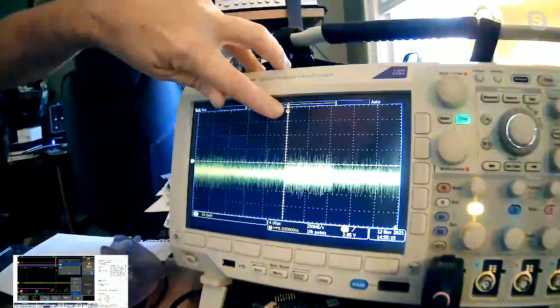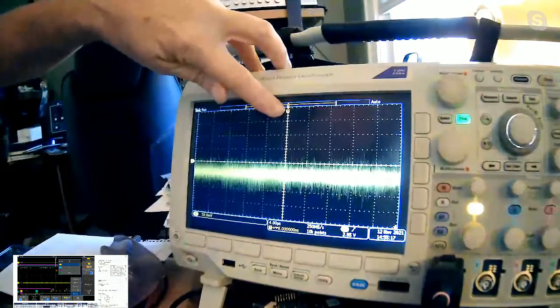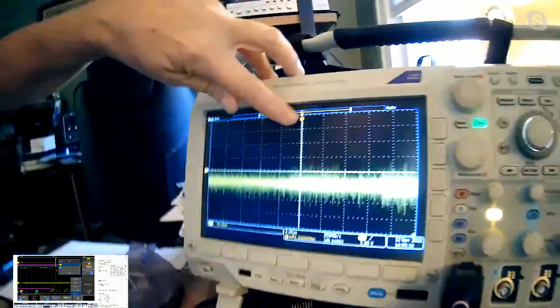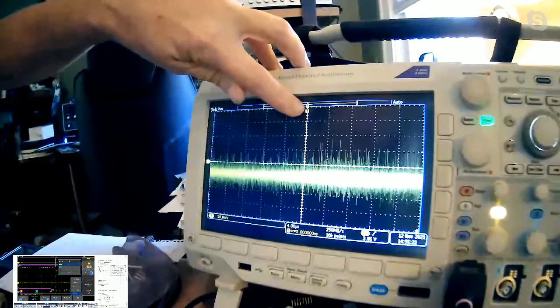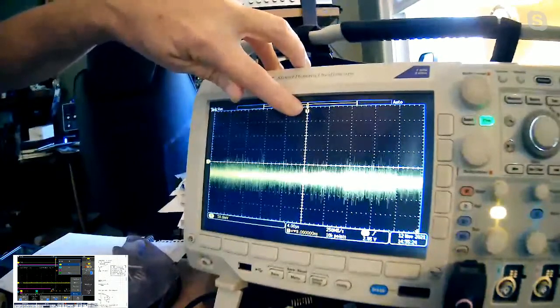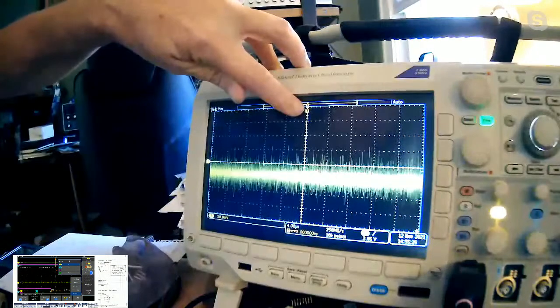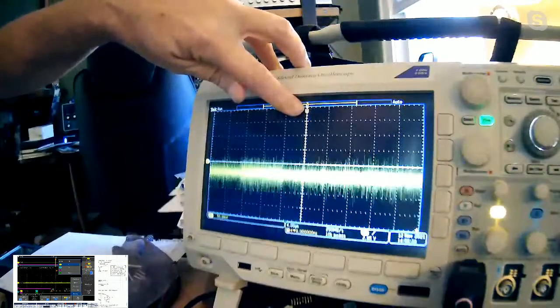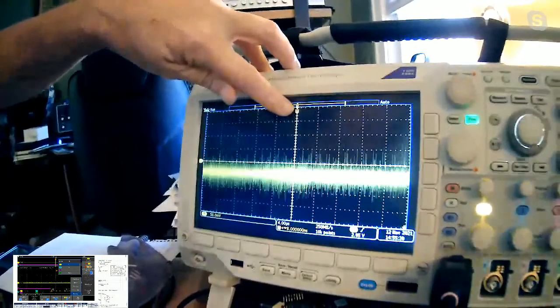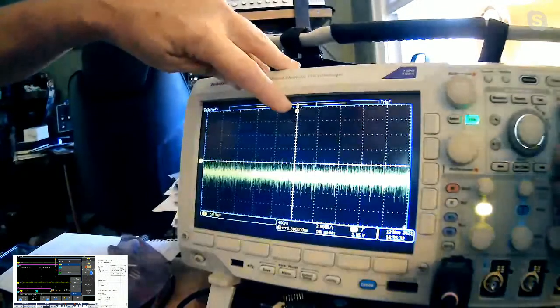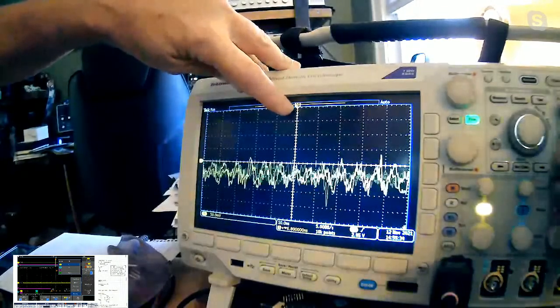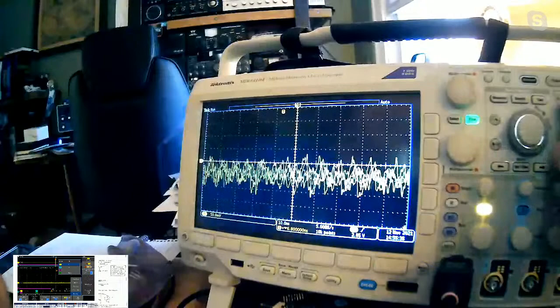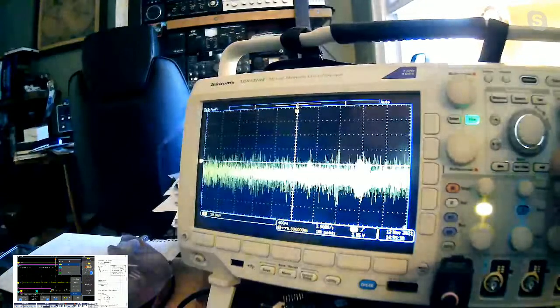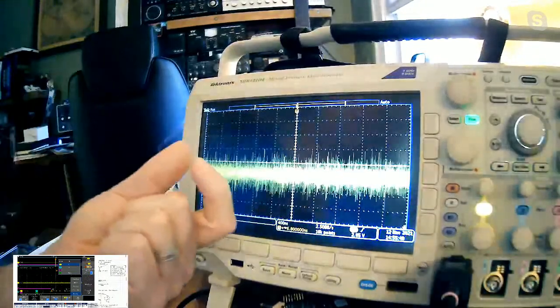Usually up in the scope, you will see a similar caret, okay? In this case, it's a down pointing caret right in the center of the screen. That's the horizontal expansion point. So what that means is if I make changes to the horizontal scale of the scope, it's going to expand and contract around that point. Most of the time, that point and the trigger location are the same location.